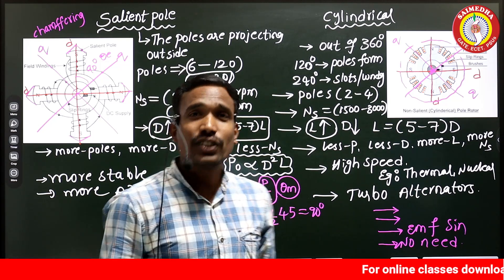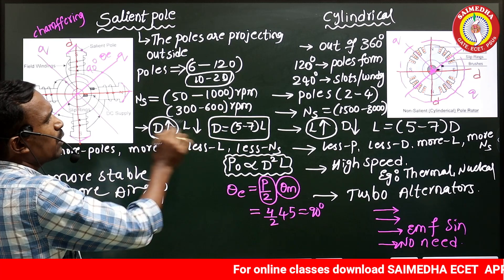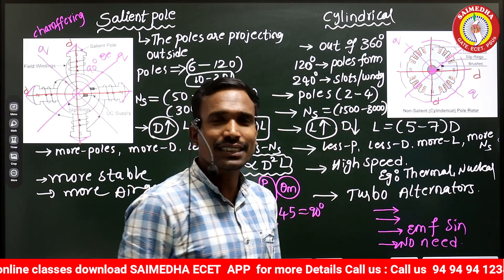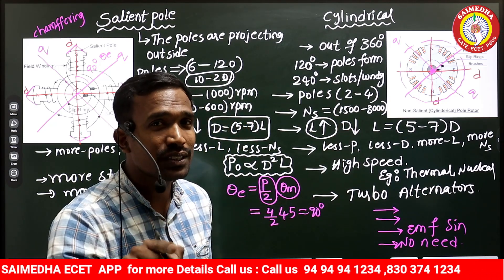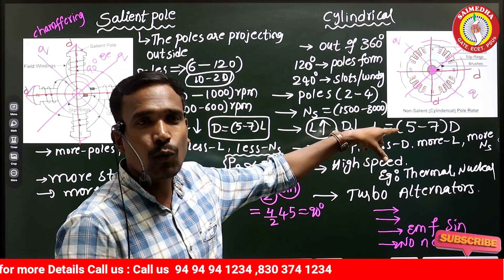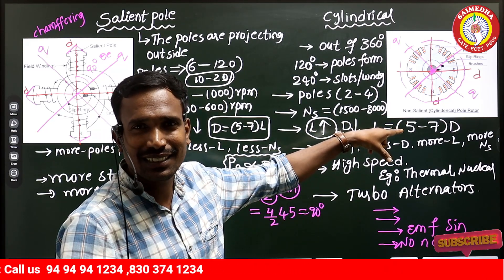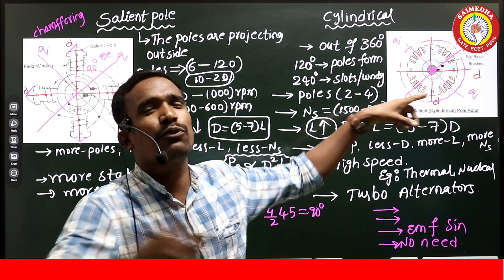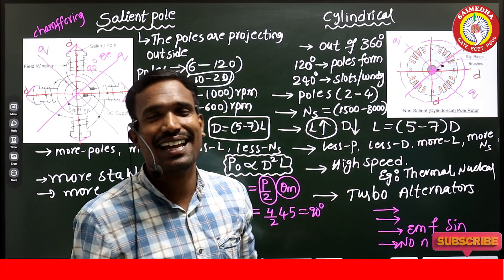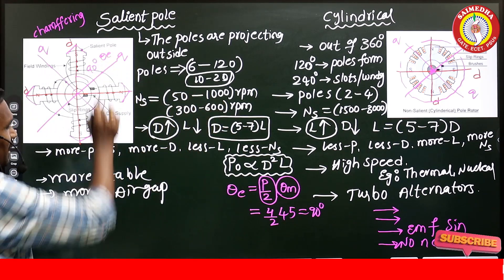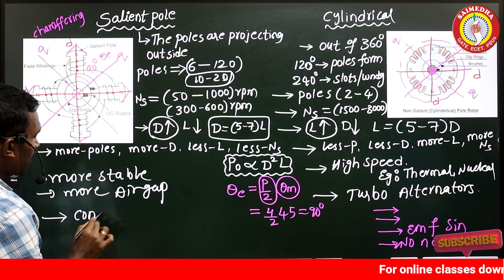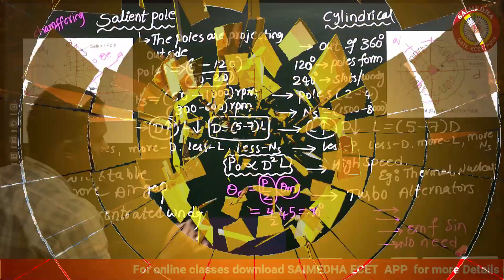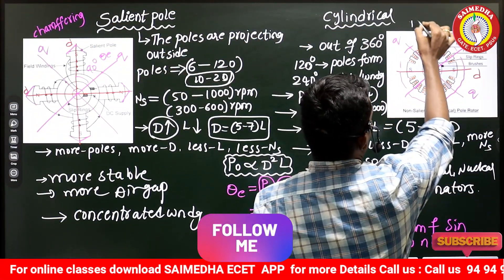Where the speed is minimum, we can use concentrated winding. Where the speed is maximum, we must use distributed winding — otherwise the winding will be dislocated or come out from the slots at high speed. So in our salient pole machine, we use concentrated winding. In the cylindrical machine, we use distributed winding.